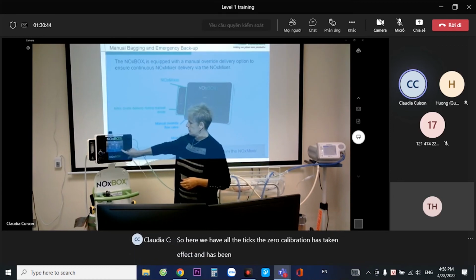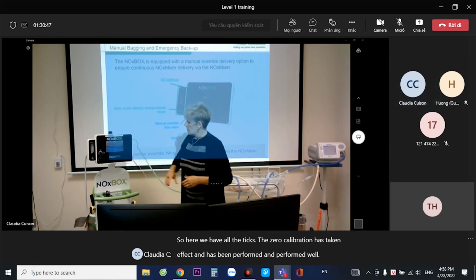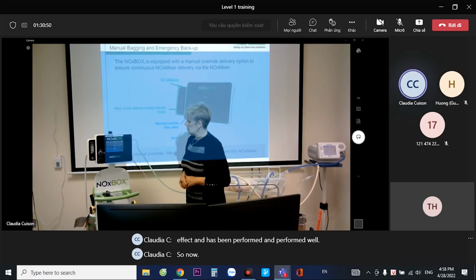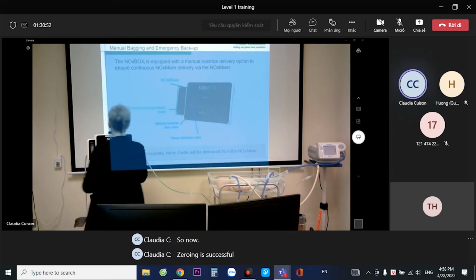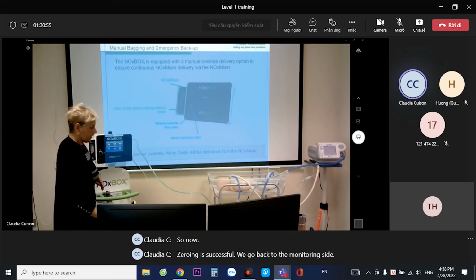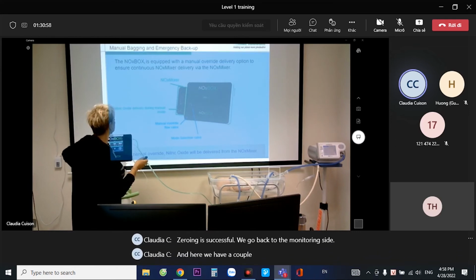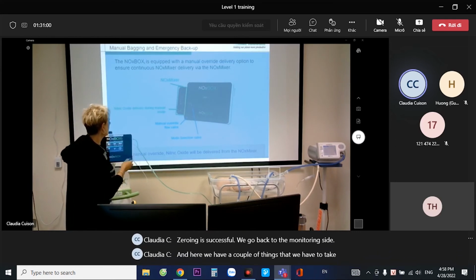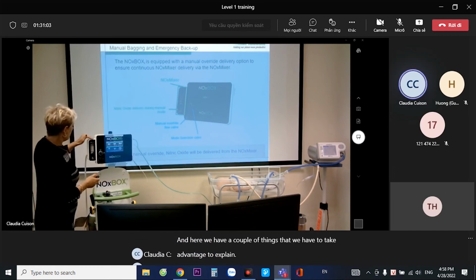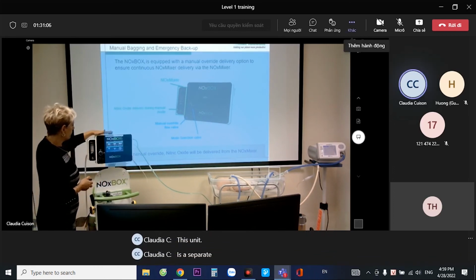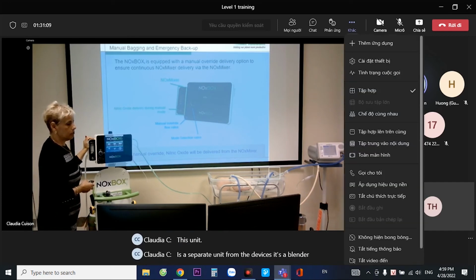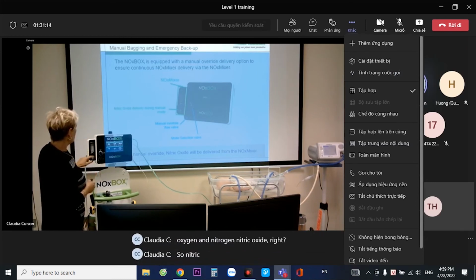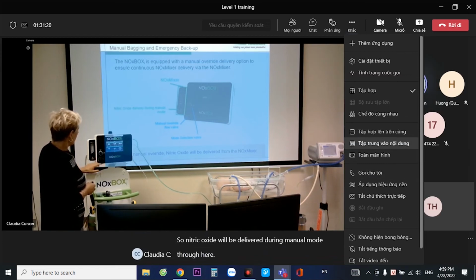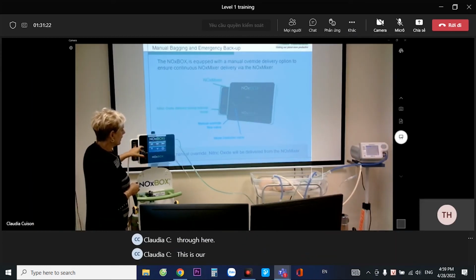So here we have all the ticks. The zero calibration has taken effect and has been performed, and performed well. So now the zeroing is successful. We go back to the monitoring side. And here we have a couple of things that we have to take advantage of to explain. This unit is a separate unit from the devices. It's a blender. It blends oxygen and nitric oxide, right? So nitric oxide will be delivered during manual mode through here.